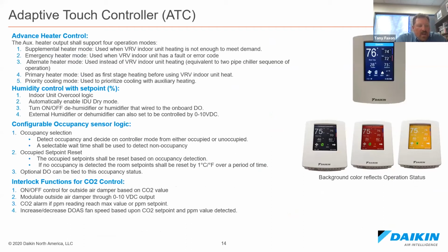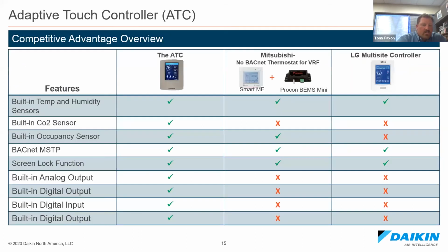The LED screen background color is going to reflect the operational status, similar to the other 2 controllers we discussed. With all the auxiliary heating options, projects with ultra low ambient temperatures, similar to the, say, -30 that we can see in mountain applications, become really simple to control. Occupancy sensor logic is also built in to increase utility savings for the owner, while advanced CO2 control is simplified with the ATC. So here again, you can see when you compare it to other competitors' options, the differences are very impressive.